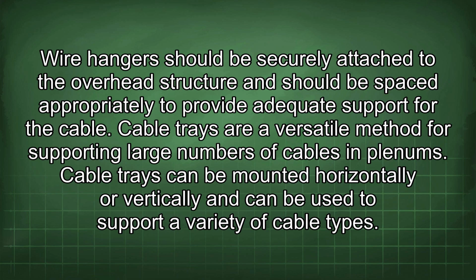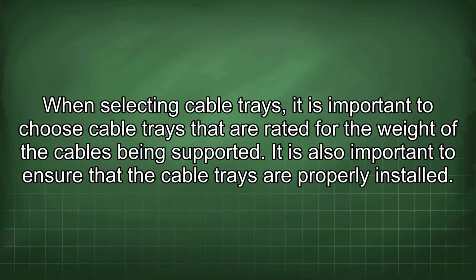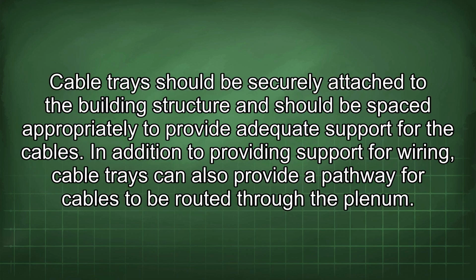the cable. Cable trays are a versatile method for supporting large numbers of cables in plenums. Cable trays can be mounted horizontally or vertically and can be used to support a variety of cable types. When selecting cable trays, it is important to choose cable trays that are rated for the weight of the cables being supported. It is also important to ensure that the cable trays are properly installed.